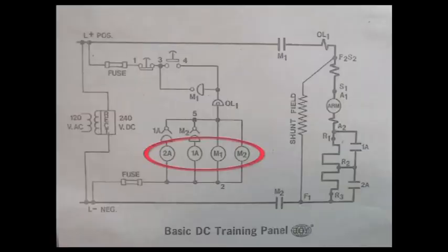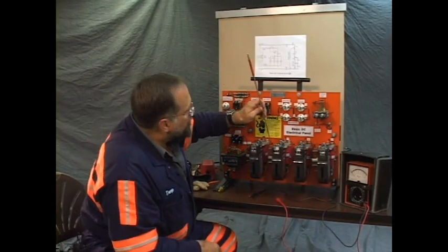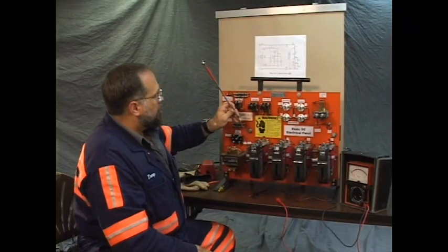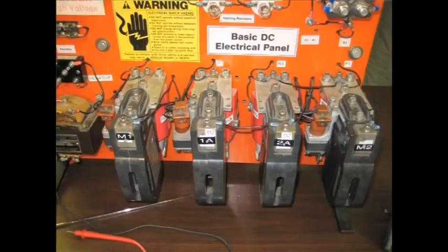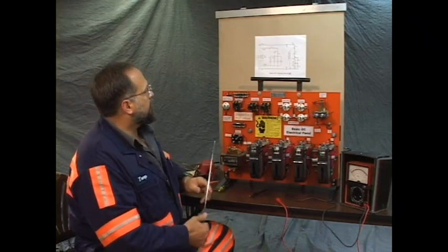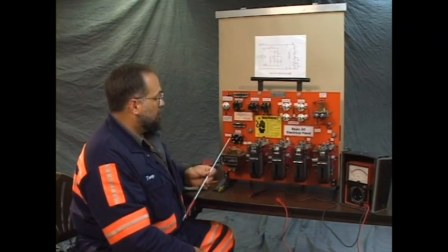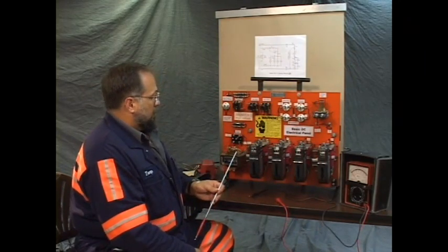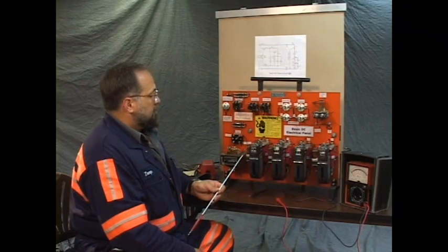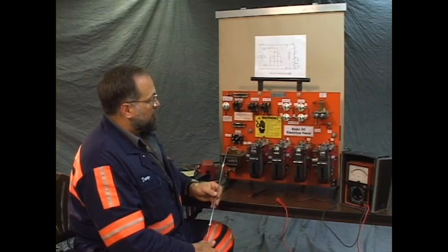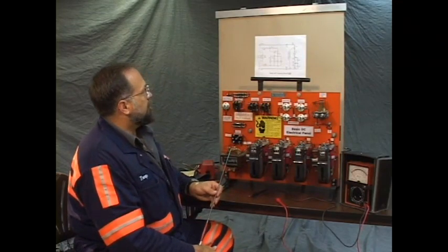Next on the drawing are 2A, 1A, M1, M2 coils. The apprentice can see these. These are red in the back. These are the coils. The control circuit, when energized, causes the coil to become energized and is an electromagnet and pulls the contact tips together.